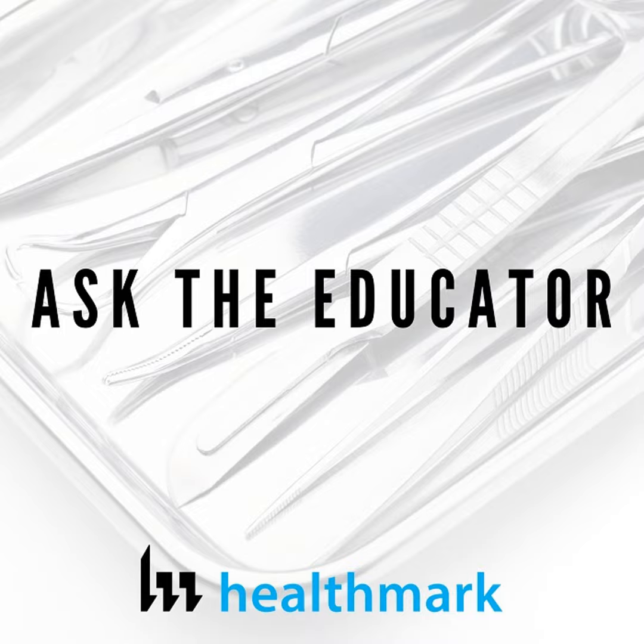What they don't realize is the pump can have water flowing through it, but if there's a broken O-ring, something not plugged in correctly, or a kink in the hose, the pump thinks it's flushing, but nothing is actually coming out. That's what you highlighted in the webinar.